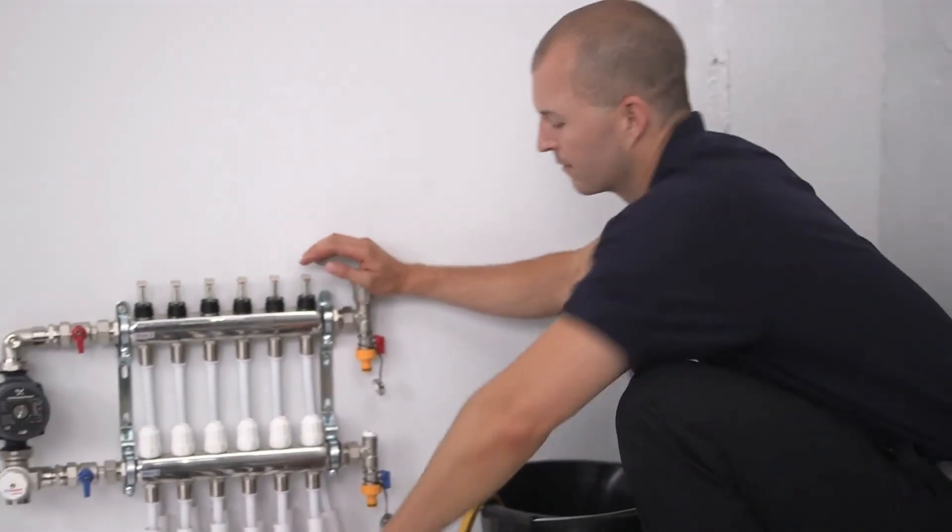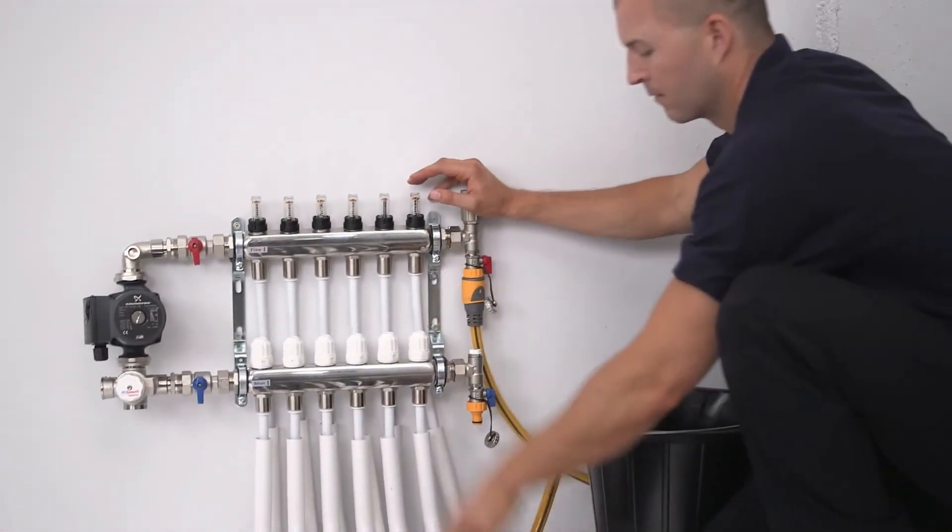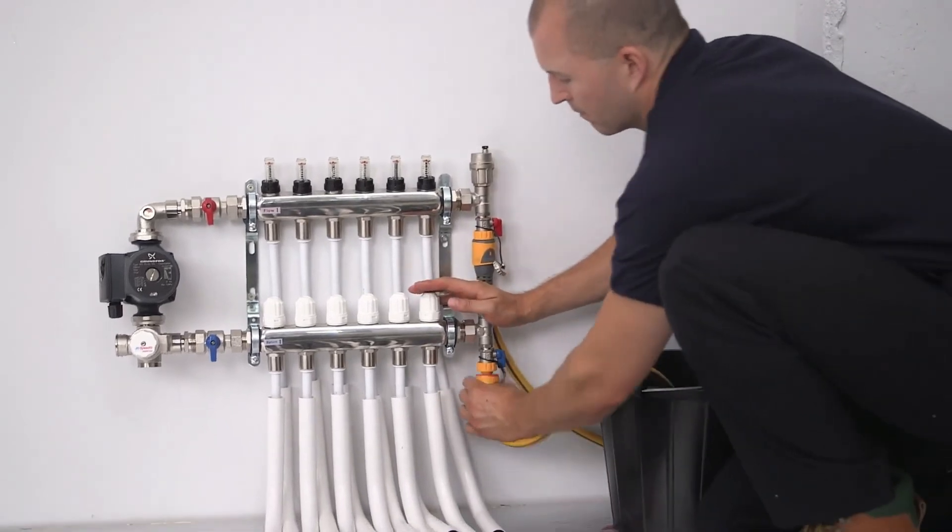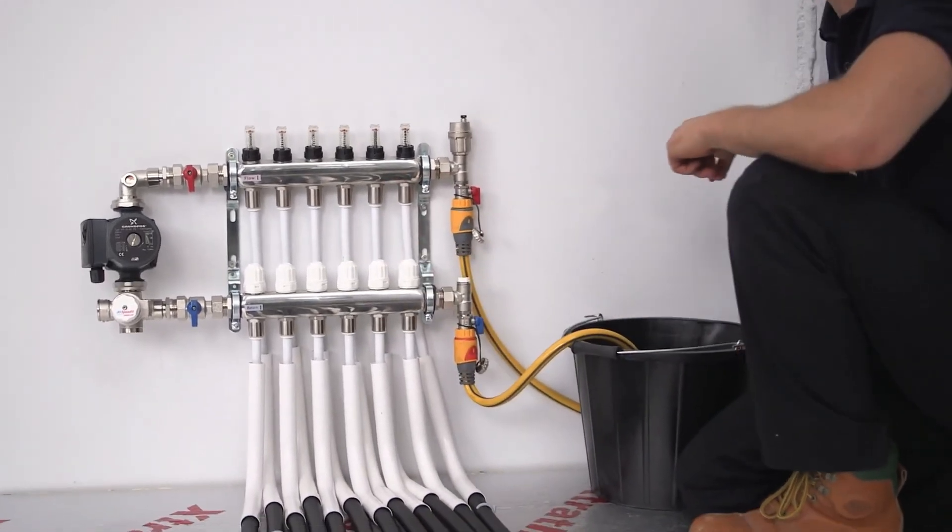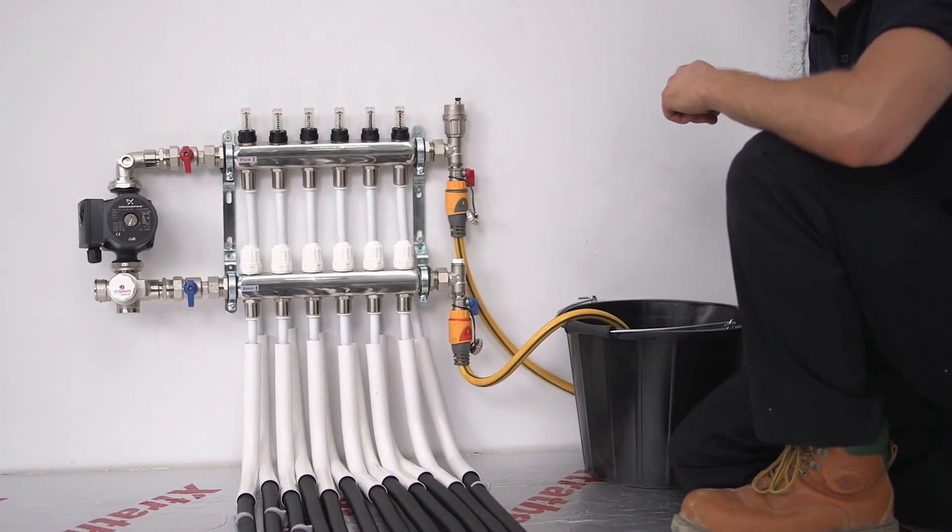Under no circumstances should the UFH be used for speeding up the drying period. If the UFH has been installed when there is a possibility of freezing conditions, suitable antifreeze should be added to protect the pipe work. The system will need to be flushed out and refilled prior to operation.